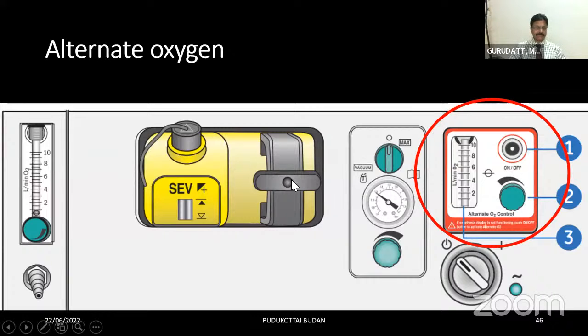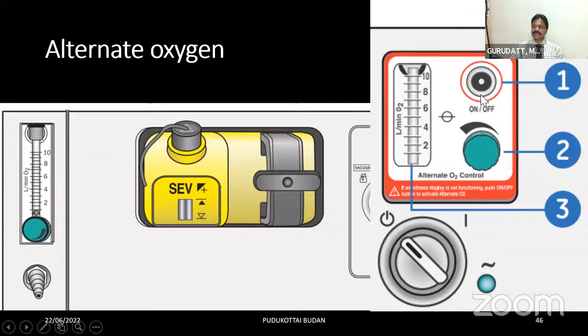In modern workstations like the Aisys CS2 machine, or even in Dräger Primus, everything is electronic, so an electronically controlled hypoxic guard will be there. Suppose by chance this electronically controlled hypoxic guard fails, then you can mechanically open up the alternate source of oxygen, called the alternate oxygen. You can see here there is alternate oxygen in GE machines, the Aisys CS2. You can just turn this on and still give 100% oxygen to the patient, up to 10 liters. You can also provide the anesthetic vapor along with that. So even if the electronic hypoxic guard fails, you can definitely use this.